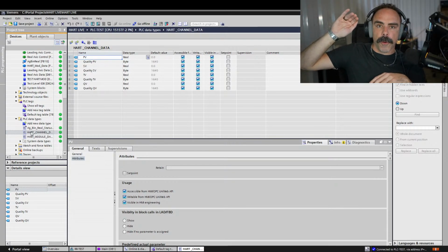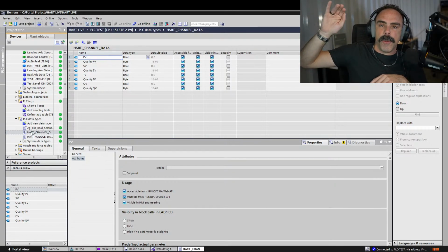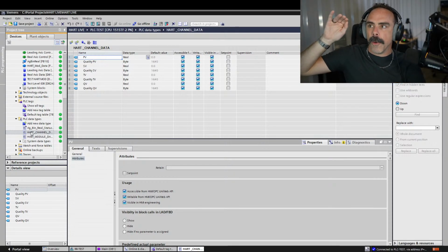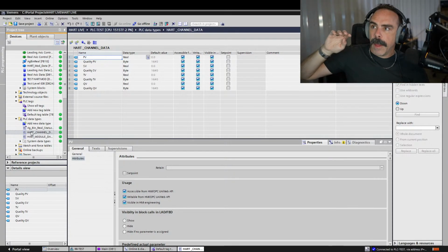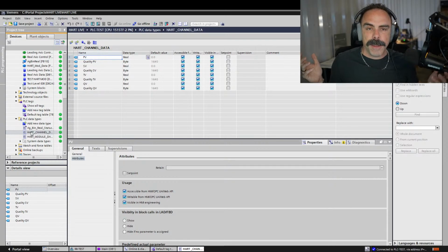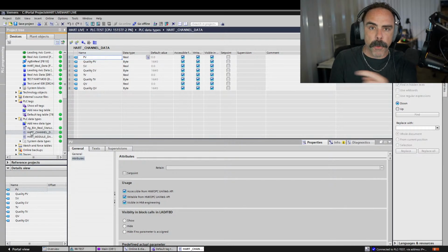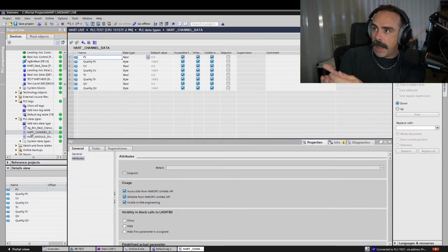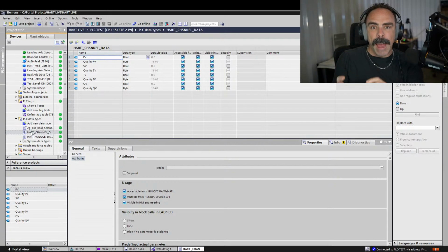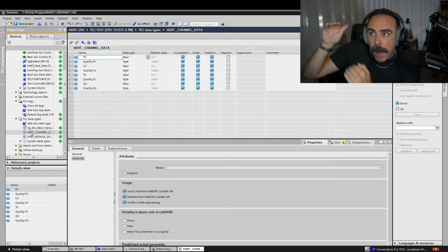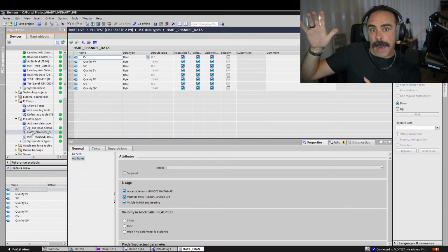You have your real value, your byte value, your real value, byte value, real value, byte, real byte. And you would think, okay, that works, Jason, right? Yeah, that's awesome. And I'll be real, in Siemens, so in Step 7 V5, so pre-portal, this was fine. And this would work. And it was easy. You could point this HART channel data to address 32 and then populate it, and it would be right.